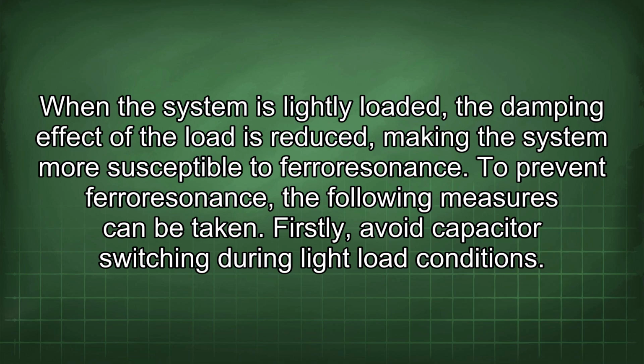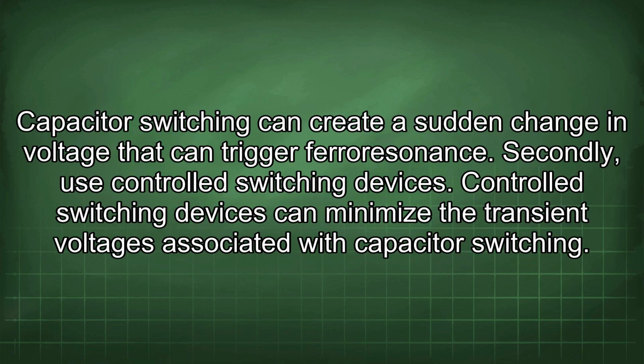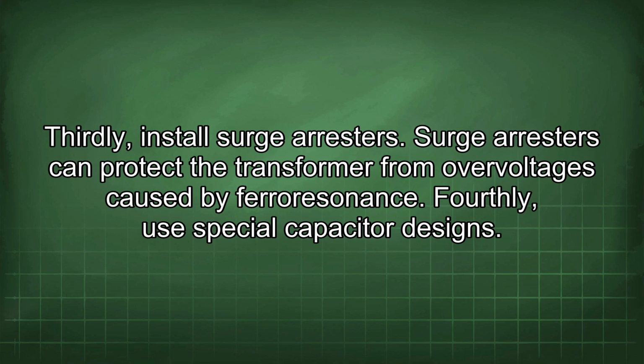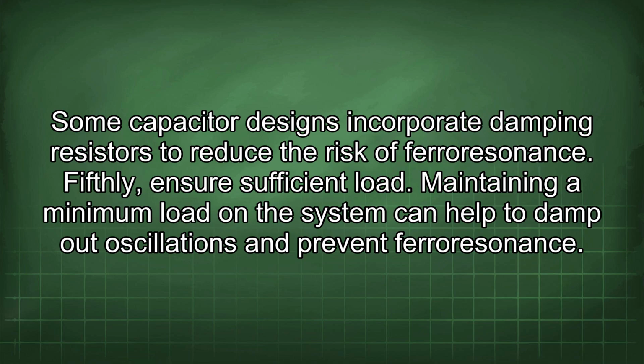Firstly, avoid capacitor switching during light load conditions. Capacitor switching can create a sudden change in voltage that can trigger ferroresonance. Secondly, use controlled switching devices. Controlled switching devices can minimize the transient voltages associated with capacitor switching. Thirdly, install surge arresters. Surge arresters can protect the transformer from overvoltages caused by ferroresonance. Fourthly, use special capacitor designs. Some capacitor designs incorporate damping resistors to reduce the risk of ferroresonance. Fifthly, ensure sufficient load. Maintaining a minimum load on the system can help to damp out oscillations and prevent ferroresonance.